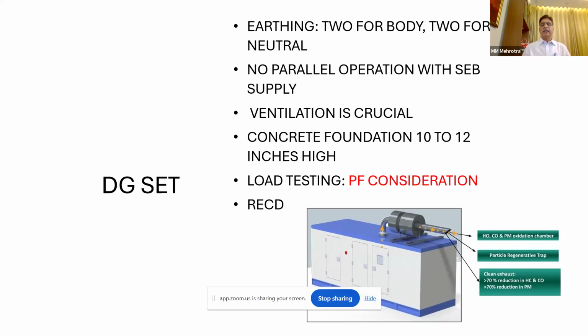Now, my DG set. Earlier, the DG set used to be open. Now, as per government guidelines, they will be encased in an acoustic enclosure, as in the case of vehicles, where Bharat 4, Bharat 5 norms come into play. So it is important that the DG set is placed on a stable concrete foundation which does not allow any vibrations. Next is ventilation. If this acoustic enclosure is kept outside, natural airflow will take care of temperature. But in multi-storied buildings, the DG set is usually kept in the basement, where ventilation is less. So there should be adequate ventilation in the form of exhaust fans and other things.